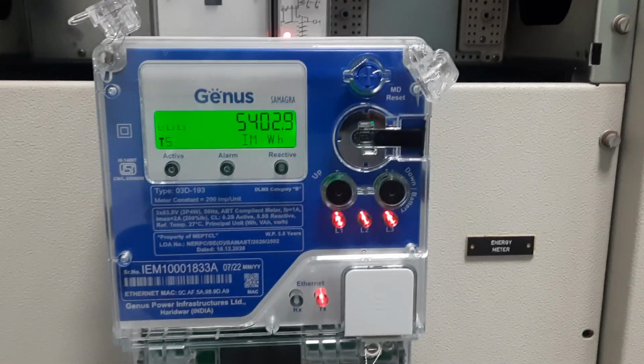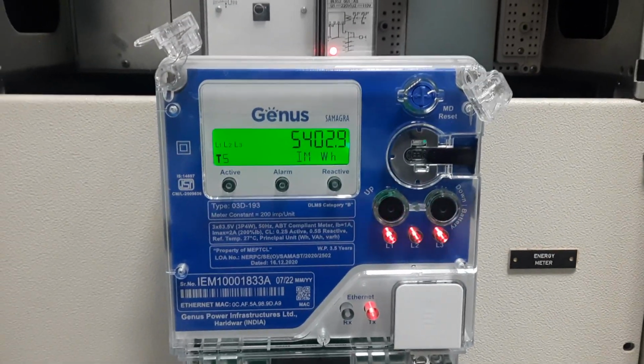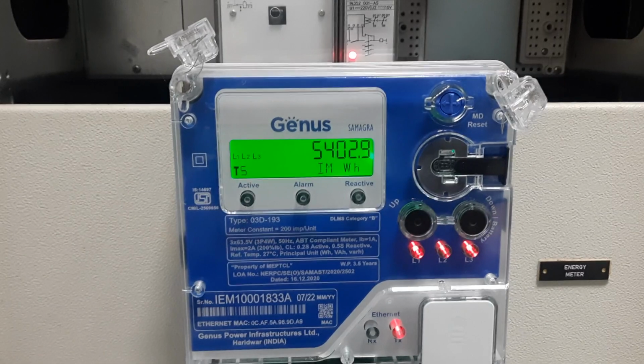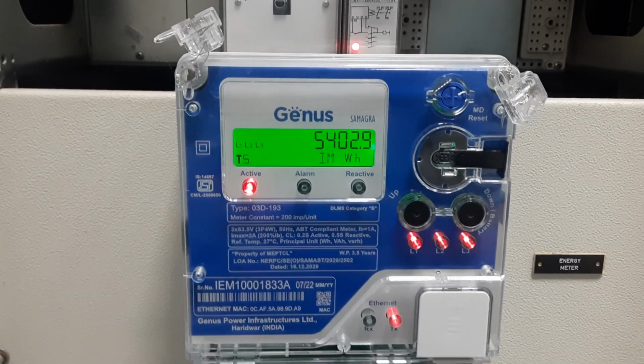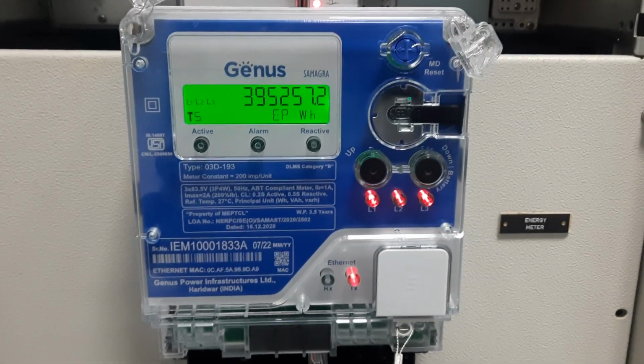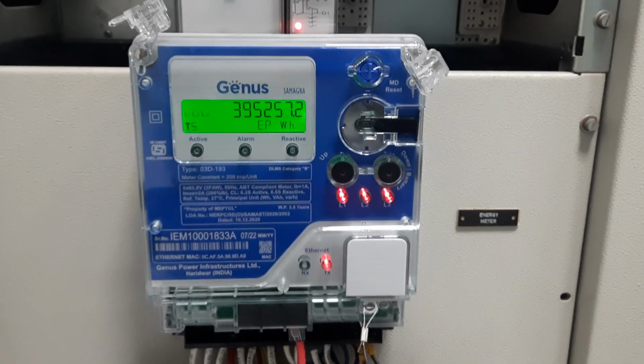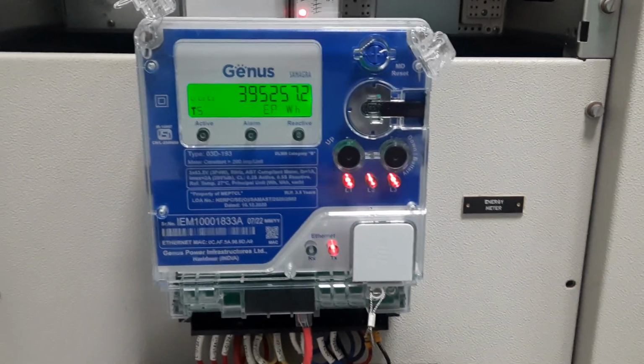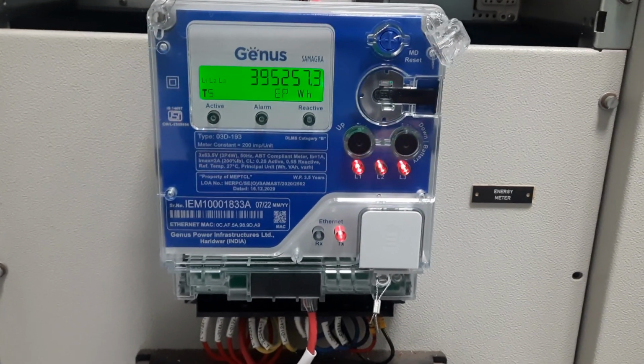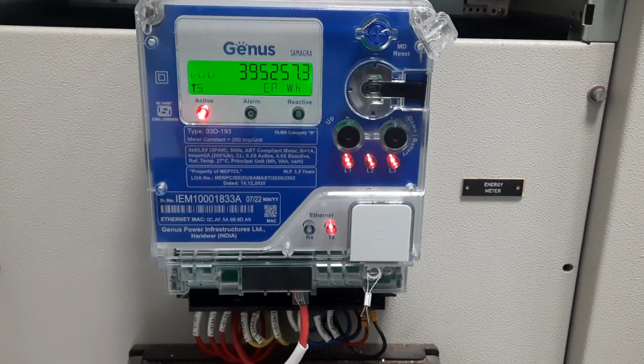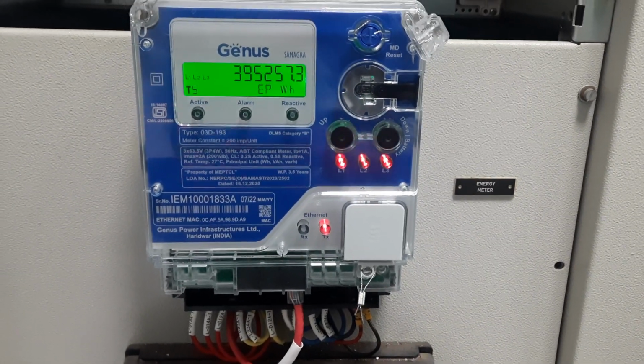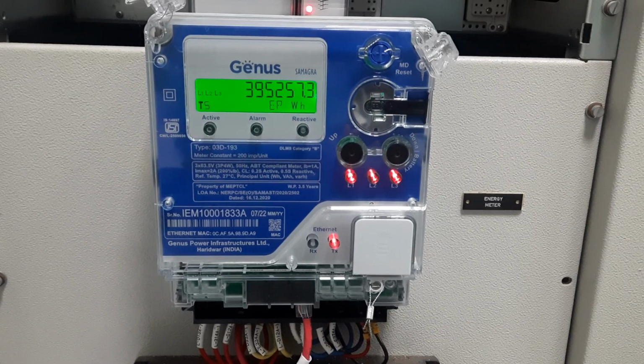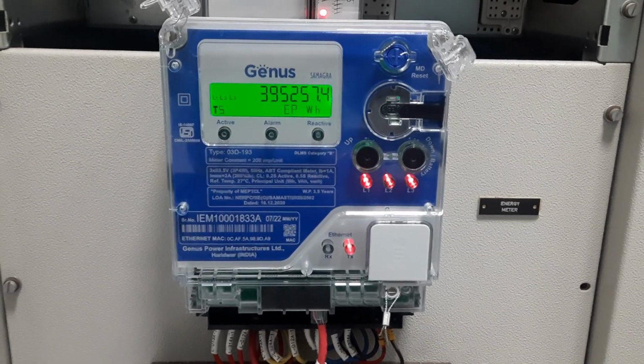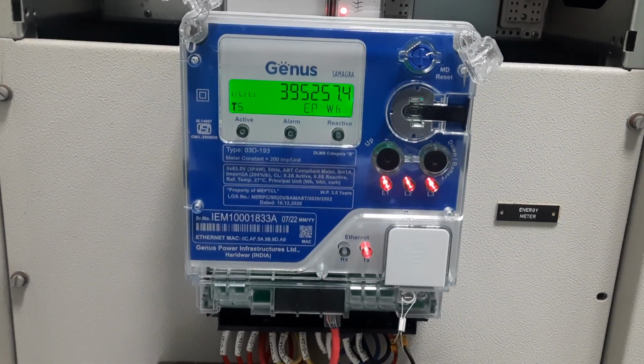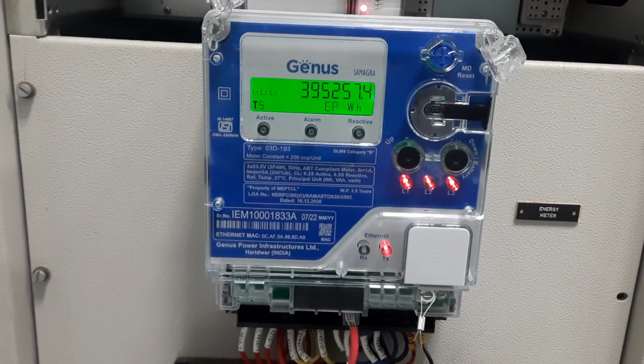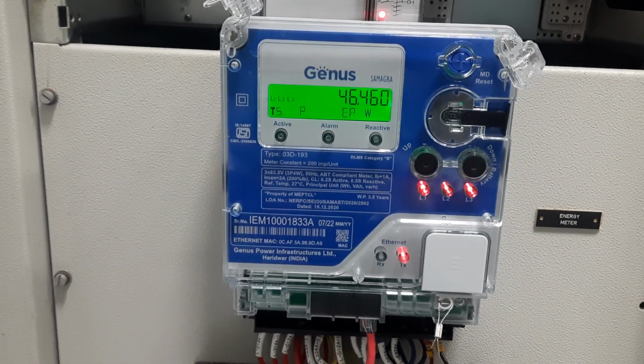This is the energy meter of 132 kV Rajabagan Line 1, that is bay number 105. Our purpose here is to verify whether the connection done to this meter is right. This is also one way of checking or inspecting whether there is any malfunctioning or any fraud in the meter connection. For that, you just have to check these two quantities, your voltage and currents, to see whether they are giving you the right values or not.